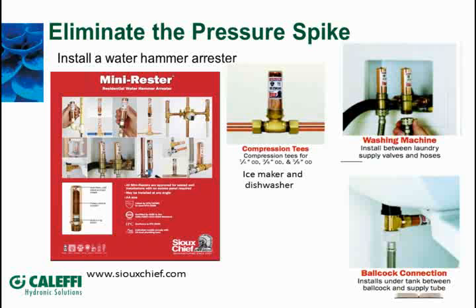Or it might be if you have an ice maker on your refrigerator and that solenoid valve in there closes off quickly, you could have a bang. Or if you have a lawn sprinkler system hooked up to your water piping and it's got solenoid valves, or it's got shut-off valves out there that shut off with a bang, it can cause that pressure spike in there, and it can cause that little cartridge to jump off its seal. So the way that you can handle that is put in a water hammer arrestor in the building.